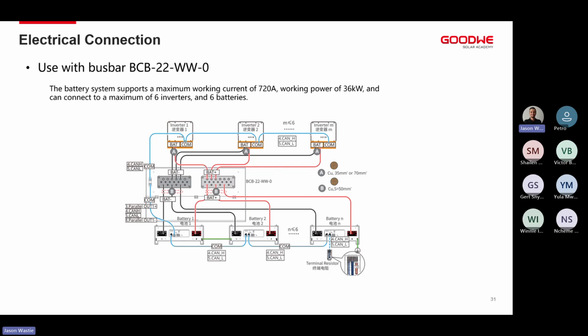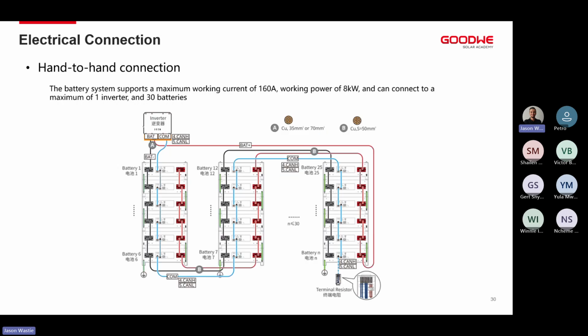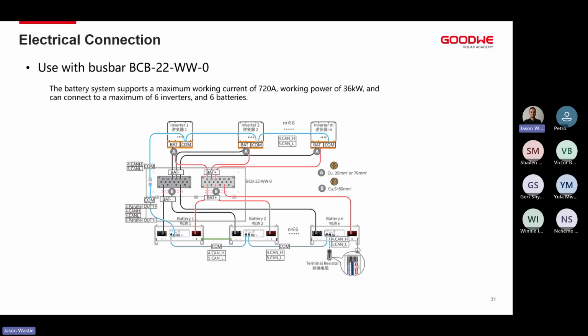If we do need to increase that output power, we can do so using a busbar. We would use a busbar for a few different things. One, it makes the installation a lot safer. Two, it makes the cabling a lot easier to deal with, and easier for maintenance and control. We do recommend this with any of our installations. If we're installing more than, say, 2 batteries, we wouldn't recommend doing the hand-to-hand connection, depending on the situation, obviously. But a busbar will always be our recommendation.